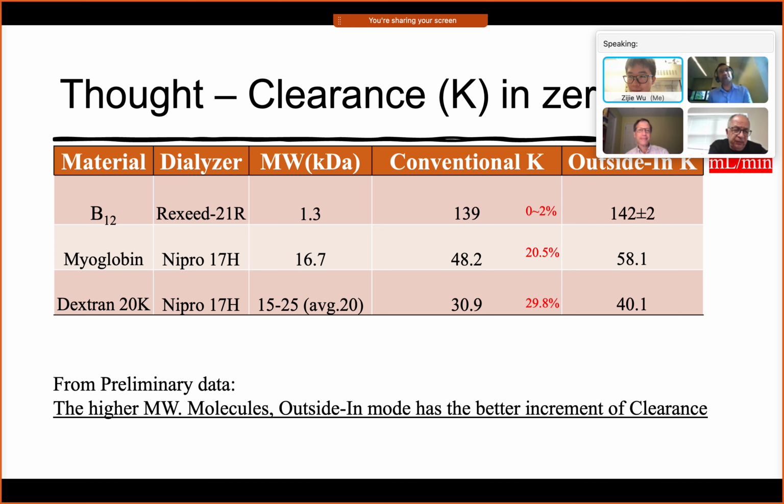Yeah, Andrew, if you run it countercurrent, there will be a crossover point between the pressures. Would that really affect the clearance result where that point of crossing is? So, if you're running with zero net ultrafiltration, the crossover point is very close to the middle of the device. And the only way to really move it is to not be running at zero net ultrafiltration.